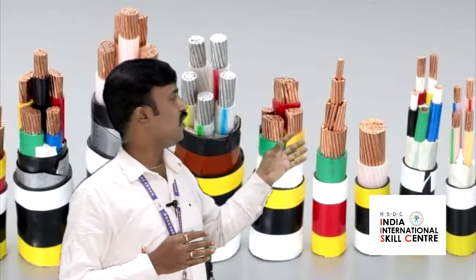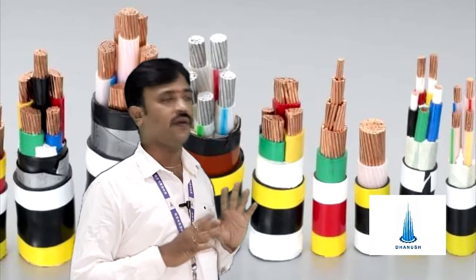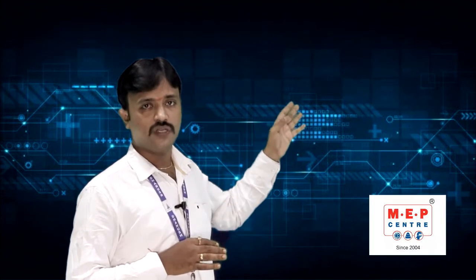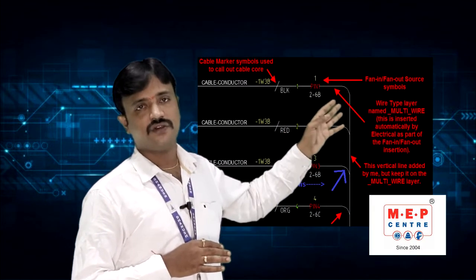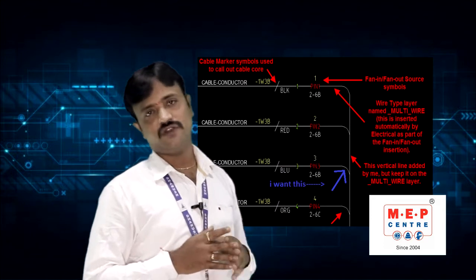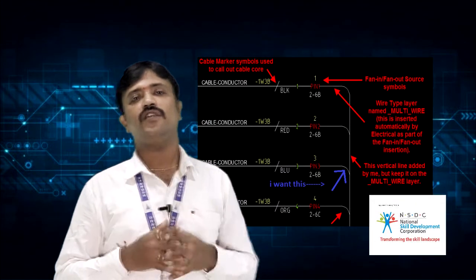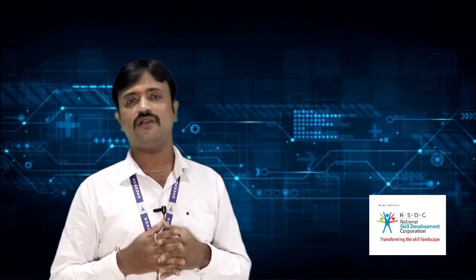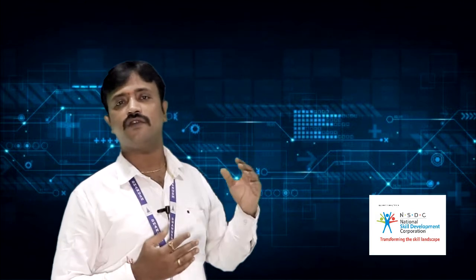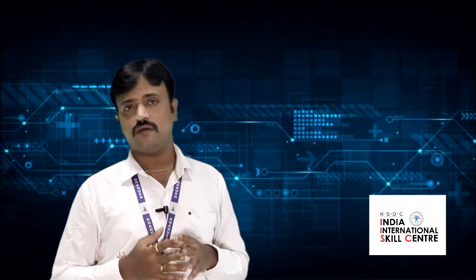So as you can see, how the cable is represented in any technical AutoCAD drawing is in terms of runs, core, square mm, and the conductor which you are using, either copper or aluminum, and the insulation which we are using. All these things we are going to study with the help of a material. So we need to take the materials, and from that material we are going to define the cable size. So we are going to study about the cable size calculation.